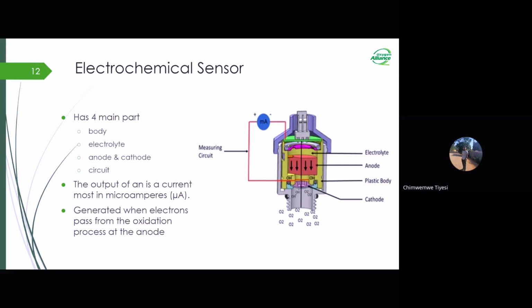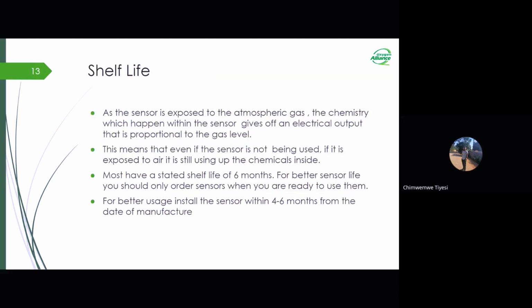I will next talk about the shelf life and storage for electrochemical oxygen analyzers. Storage life is a very important aspect to consider when deciding when and how to purchase replacement electrochemical oxygen sensors for an analyzer, or when you want to buy the sensor on its own. These oxygen sensors work by a chemical reaction that happens inside the sensor. So when the sensor is exposed to atmospheric gas, chemistry happens inside the sensor, which then gives out an electrical output. This means that even if the sensor is not being used, if it is exposed to air, it is still using up the chemicals inside.